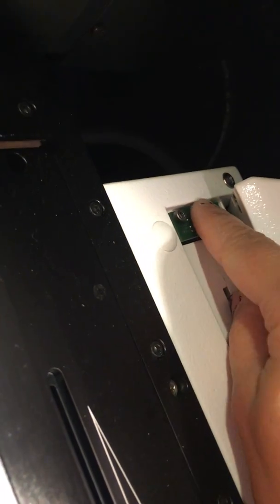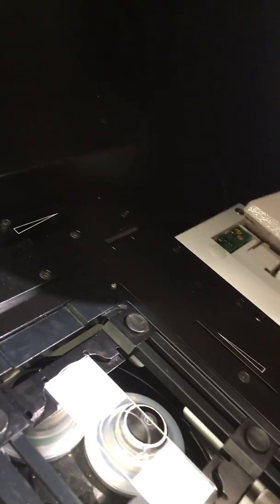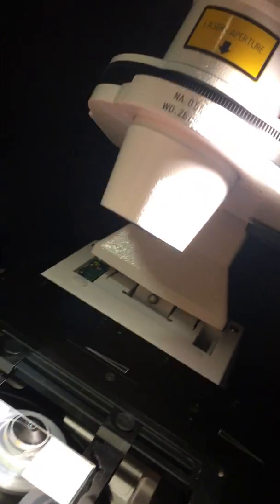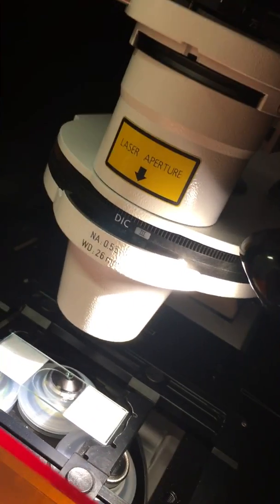Here on our 780 there are two contacts which need to make contact with these two thingies here. This is a safety measure preventing the laser coming from the lens while the head of the microscope is tilted backwards. On our 800 we have a different type of safety measure, but please put back the head of the microscope very gently in order not to crush these contacts.